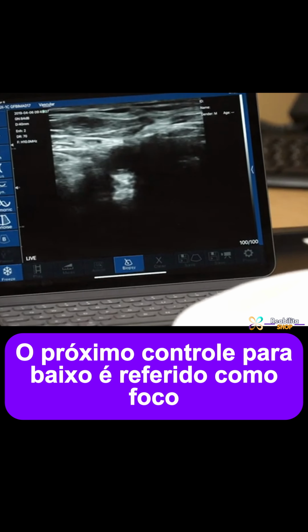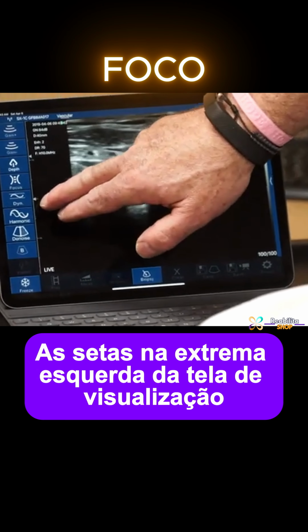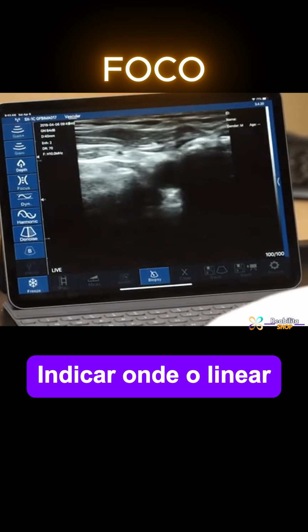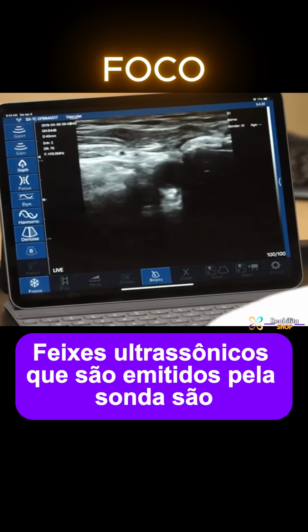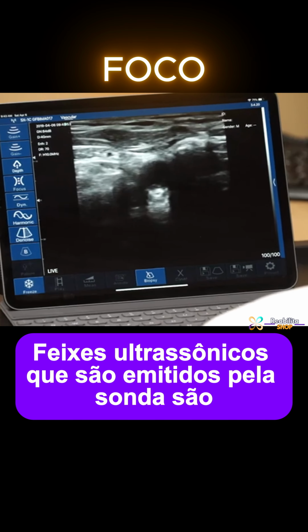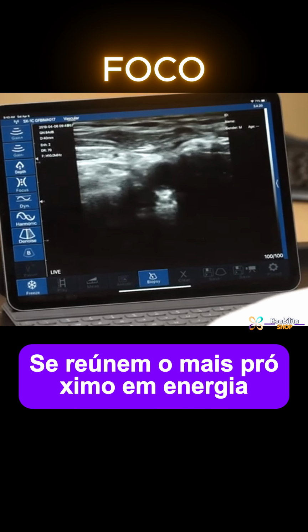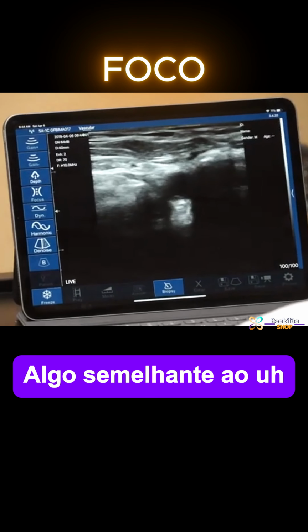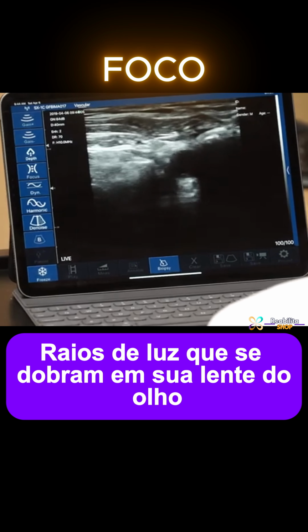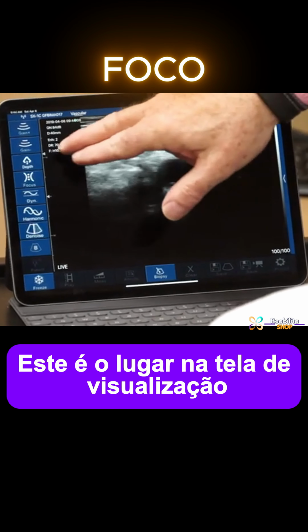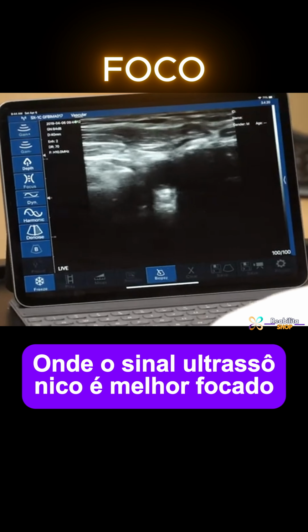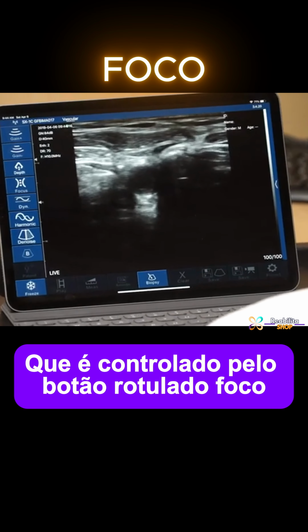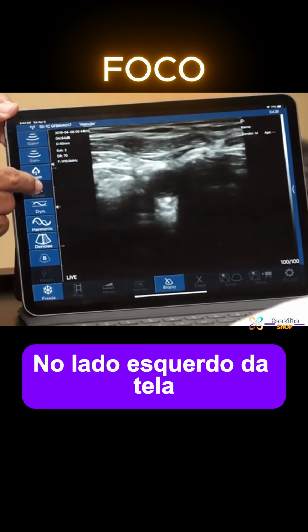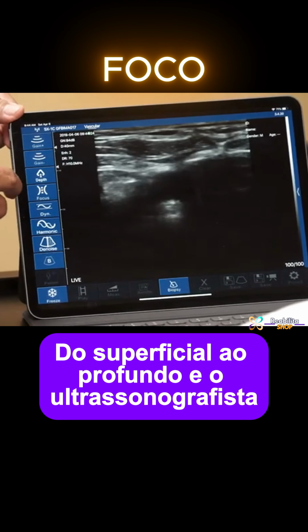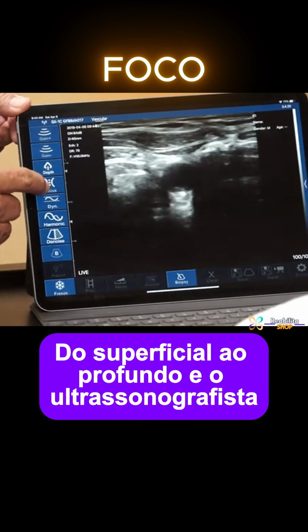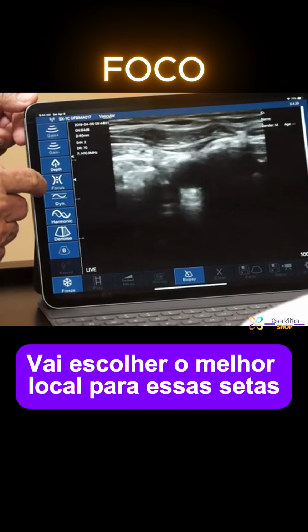The next control down is referred to as focus. The arrows on the far left of the viewing screen indicate where the linear ultrasonic beams that are emitted from the probe come together the closest in energy, highlighting a focal point, something similar to the rays of light that get bent by the lens of the eye to focus them into a point. This is the place on the viewing screen where the ultrasonic signal is best focused in intensity. That's controlled by the button labeled focus. If you watch closely, the arrows on the left side of the screen will change their position from superficial to deep, and the ultrasonographer or provider will choose the best location for those arrows based on the target of the image.